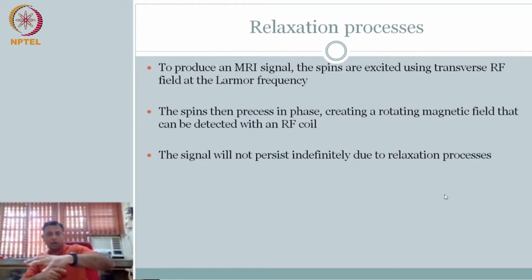That is your transverse component. There is another process also, right? Once the signal coherence is gone and the signal is going down in the transverse plane, your Z axis is getting built up. Your longitudinal component is building up. That is relaxing to gain signal strength, whereas the XY components relax to lose signal strength, right?